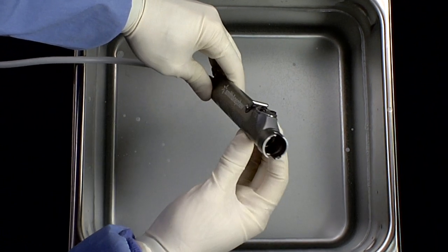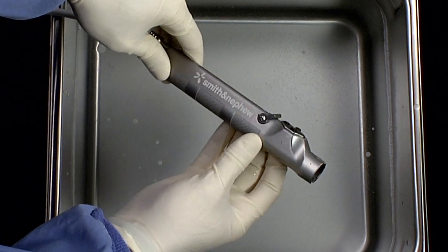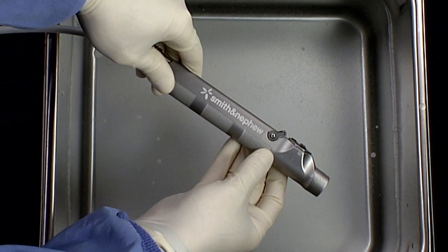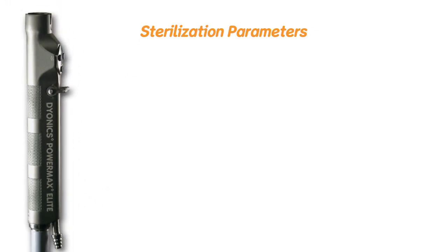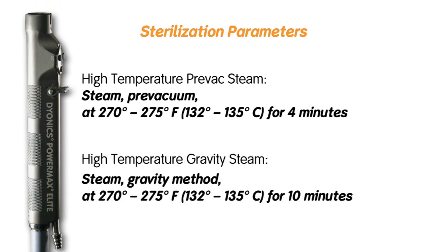For difficult-to-view areas, 3% hydrogen peroxide may be applied — bubbling is evidence of the presence of blood. Rinse instruments thoroughly with warm tap water following any hydrogen peroxide testing. Sterilization parameters: Dyonics handpieces must be sterilized by steam using one of the following methods only. High temperature pre-vac steam at 270 to 275 degrees Fahrenheit, or 132 to 135 degrees Celsius, for 4 minutes.